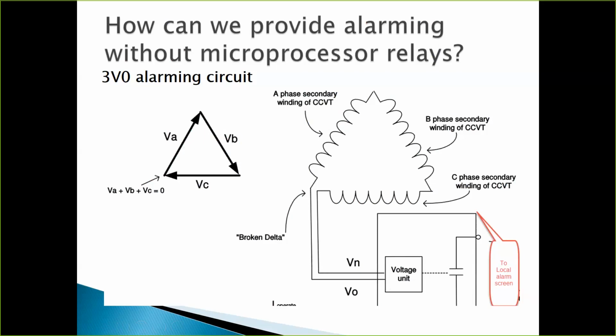So it's relatively easy. It requires some wiring, a low skill set right here. All you need is to series the windings, run some wire, a relay, and an output, and tie into your system. And we use this zero sequence alarming where we have electromechanical relays. This is our go-to source. We use these for our bus voltage indicators, where we don't typically tie into a relay. So it's a very simple circuit, very easy to do. And this is how we deploy it.